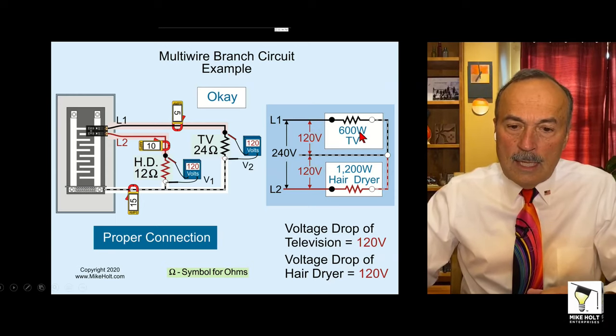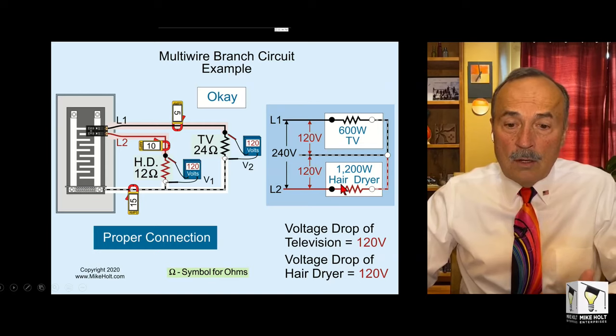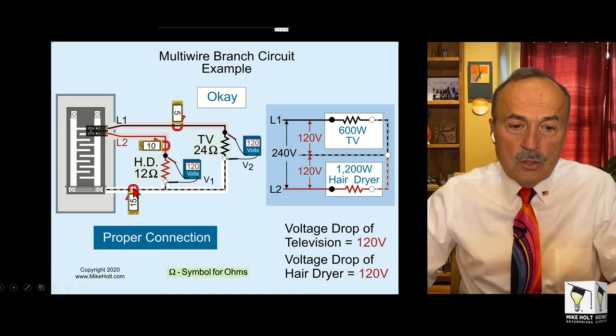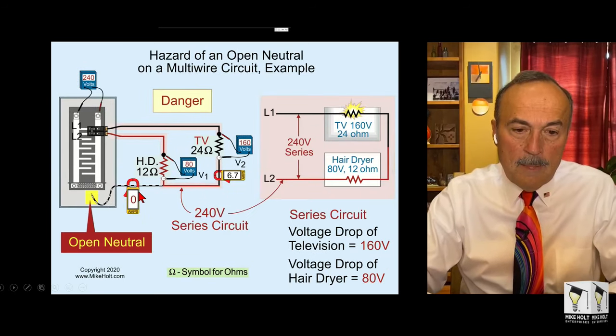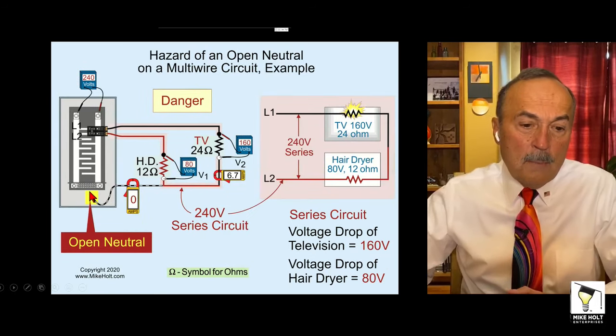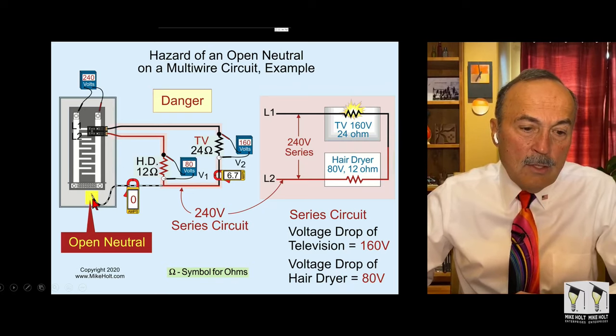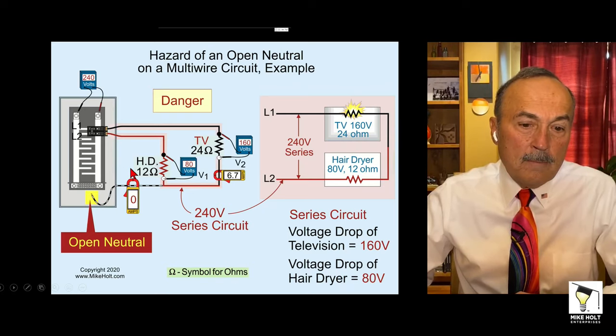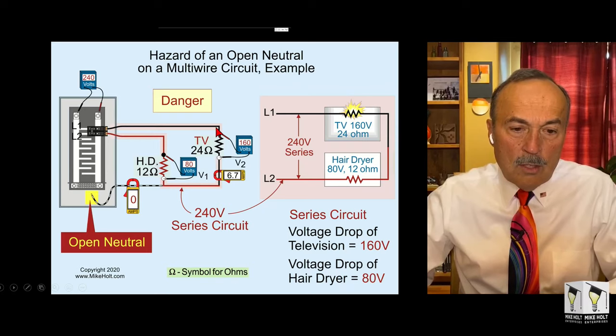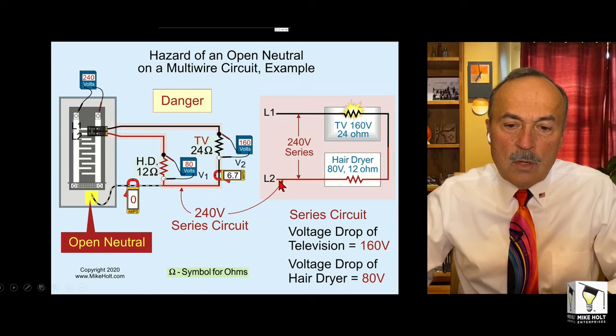Then here's another way to look at that. A 600 watt TV at 120 volts is going to be 5 amps. A 1200 watt hair dryer on 120 volts is going to be 10 amps. Neutral current cancels. Neutral current is not additive. Apologize for that. So now what happens if you're in the panel, however, and you take the neutral off of the neutral bus? Well, now you have current going out on the hot, traveling along the neutral portion with the other circuit and coming back on the other circuit. You now have what is called a series circuit.